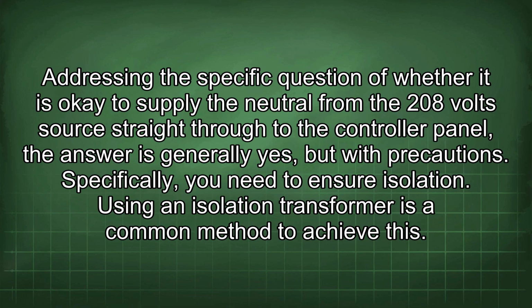Addressing the specific question of whether it is okay to supply the neutral from the 208-volt source straight through to the controller panel, the answer is generally yes, but with precautions. Specifically, you need to ensure isolation. Using an isolation transformer is a common method to achieve this.